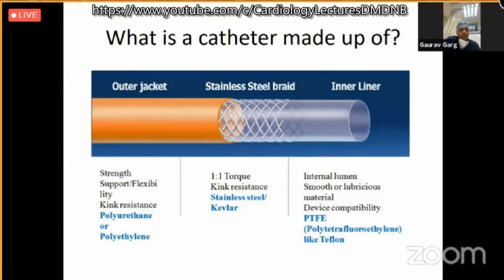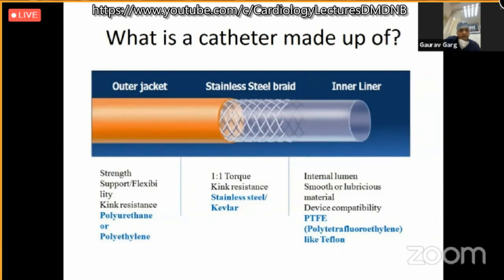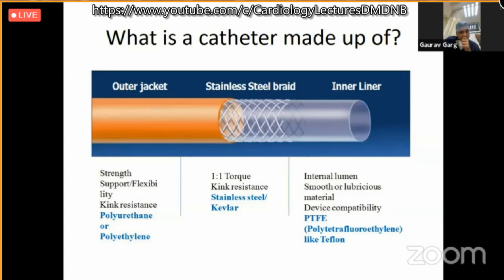What material is a catheter made of? It has an outer jacket, stainless steel braiding, and an inner layer. The outer jacket is usually made up of polyurethane or polyethylene, though some manufacturers use Dacron. The outer jacket gives strength, flexibility, and kink resistance. Braiding is done so we can give adequate torque and maintain kink resistance. The internal lumen is usually made up of PTFE for smoothness, device compatibility, and to avoid water absorption.